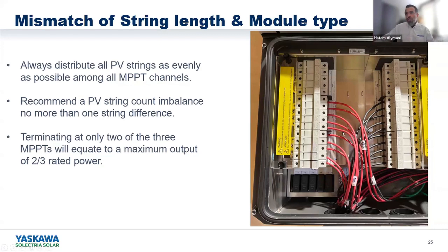So the easy solution here is just to distribute it equally. So we have, let's say, three and four strings. This way, you'll be able to maximize the inverter, and your inverter should be providing you with the full 60 kilowatts. This is an issue that we usually get from end users telling us, "Hey, I have a 60 kilowatt inverter, but the inverter is only producing 40 kilowatts. What's going on?" And as soon as we open the wiring box and take a picture of it, we see this practice, where they are all jammed in just two MPPTs, and the third MPPT is not being used. So we always recommend distributing it.